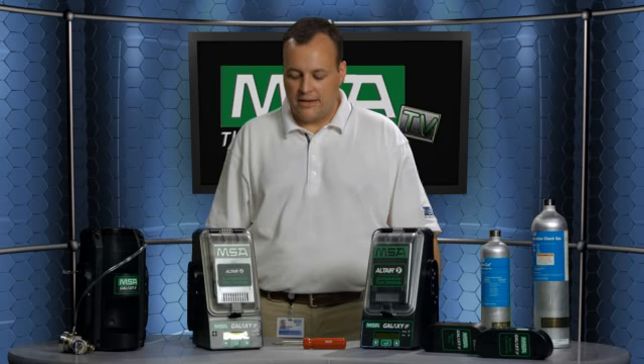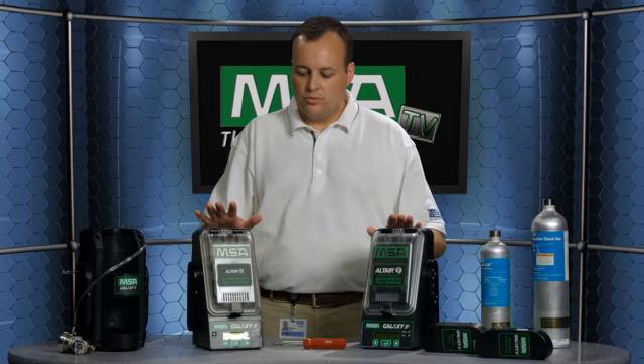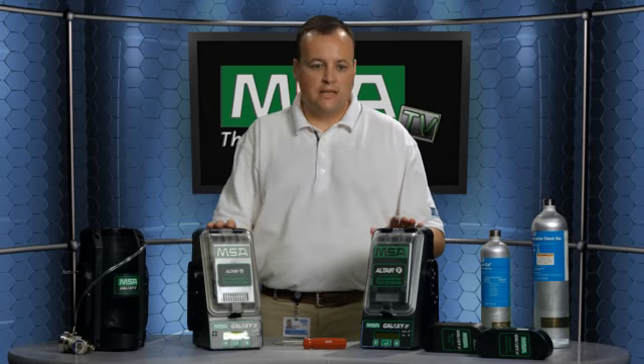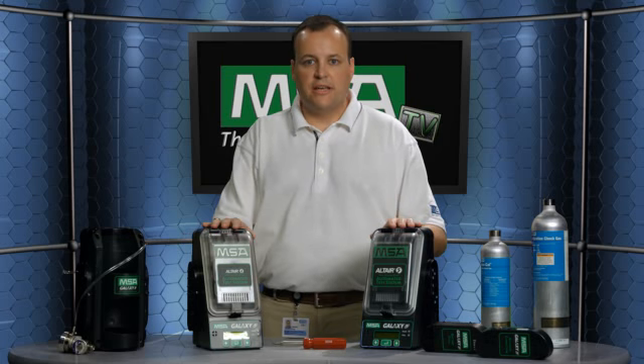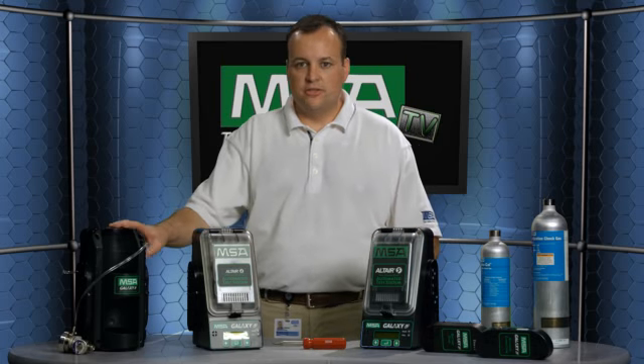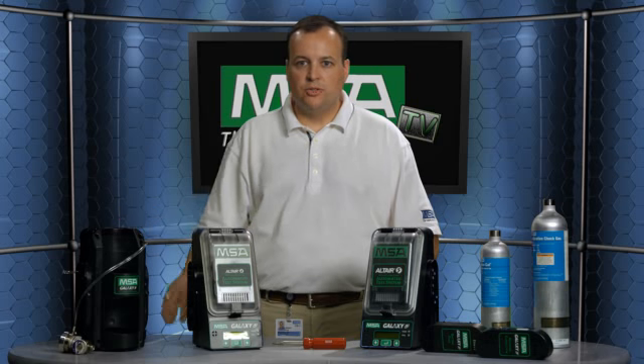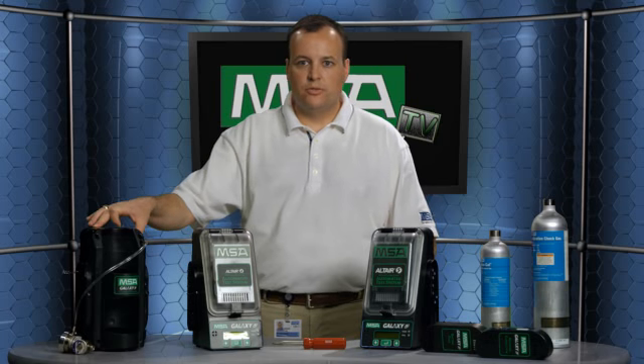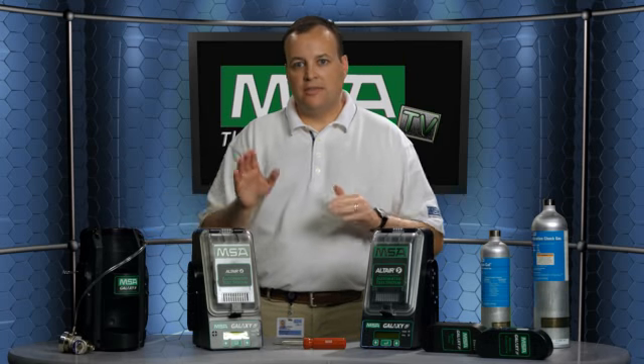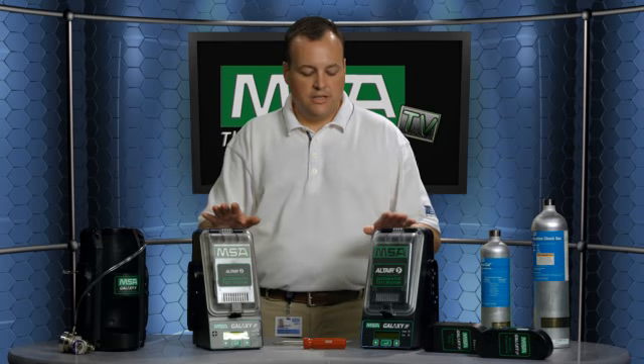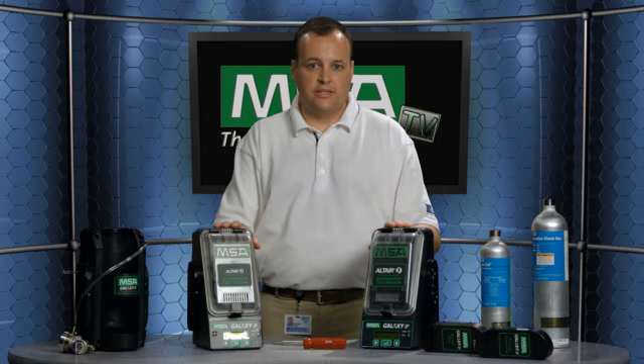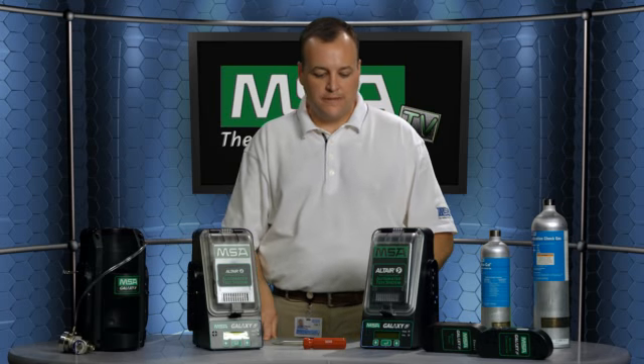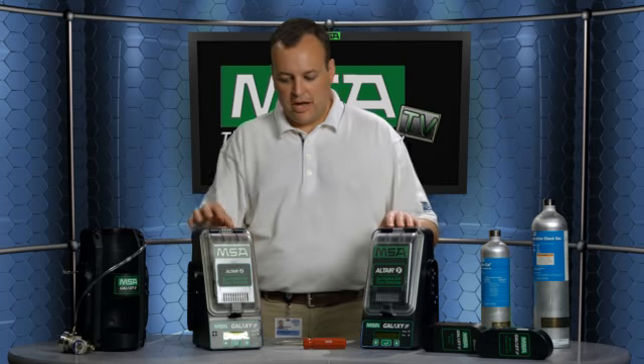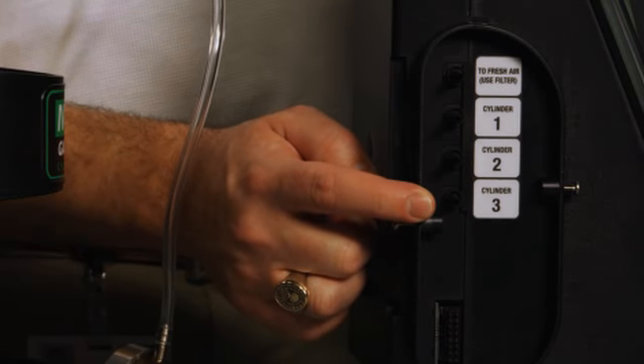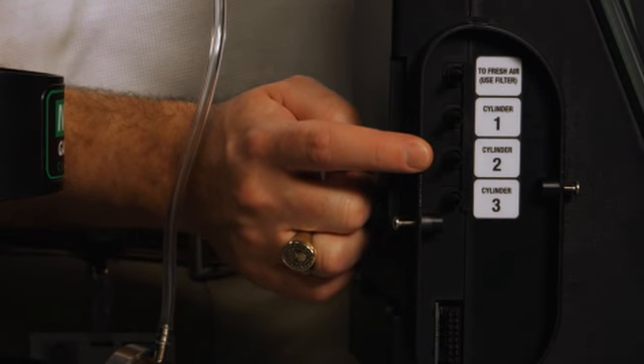You basically take it out of the box. There are two primary components of a Galaxy bank. The first is a test stand or test station, and then the second is a cylinder holder. You can have up to 3 cylinder holders, which as you look at the bank of Galaxies would be going off to your left, and then you can have up to 10 different test stands, which again as you look at that Galaxy bank will be going off to your right. So you just take them out of the box. You would make sure all your plugs are removed as you connect them through.